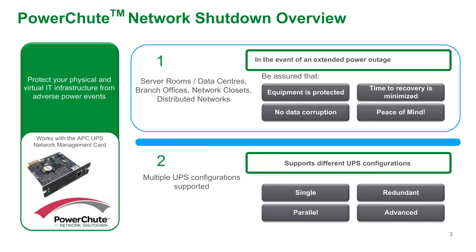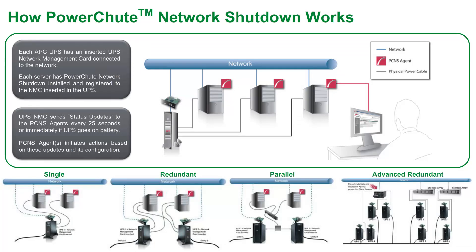PowerChute Network Shutdown works in conjunction with the APC UPS Network Management Card to protect your physical and virtual IT infrastructure from adverse power events. The software is widely deployed in server rooms, data centers, branch offices, network closets, and distributed networks to protect IT equipment during a power outage, minimizing time to recovery. Single, redundant, parallel, and advanced UPS configurations are supported. This first diagram shows a standard single UPS with a network management card inserted in the smart slot protecting three servers, each with a PowerChute Network Shutdown agent installed.